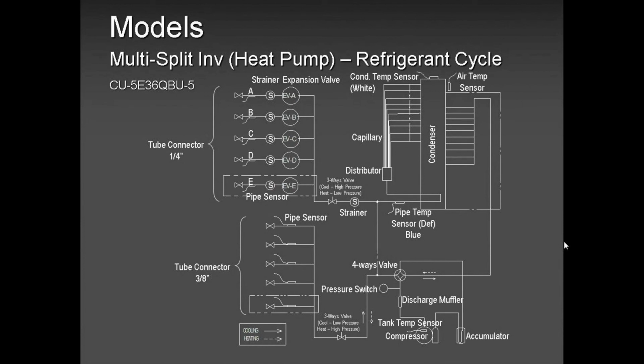So guys, when you have a cross wiring issue, it is very easy to fix. How is it easy to fix? By turning on unit by unit, 1 unit at a time. Don't run all the units together, because when all indoor units are running together, you will not catch the problem. And if you're running them in heat mode, it's even worse, because in heat mode, there is no such error as cross wiring. Only in cool mode, which is the H39 I mentioned, or the F17, standby during freezing. We'll talk about it later.